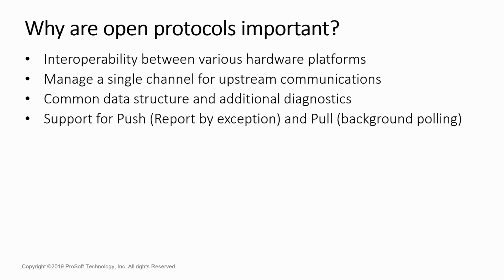Many of these open protocols support both push and pull technology. Push is report by exception, where the device can initiate the message to send data to a top end, and that's a critical part of IIoT. Pull is more like a background health check, to confirm the device is working.